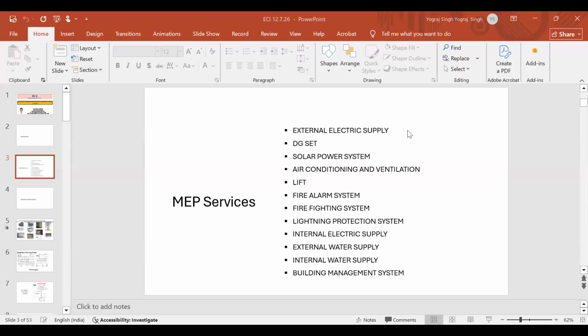There is one thing, the APFC panel, which I will introduce a little later. This power factor improvement has been made mandatory by all electricity boards and authorities. As you know, the better the power factor, the better the efficiency of the supply system. Otherwise, if 100 kilowatt is the real power, say a rolling mill rolling steel creating real power, there is some additional energy which the system has to provide because of the presence of the transformer and other things, so that will be a little more. If the power factor is as close to 1 as possible, then the power utilized and the power provided by the system will be the same.